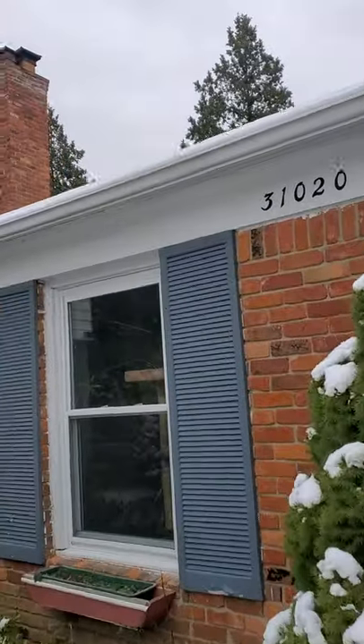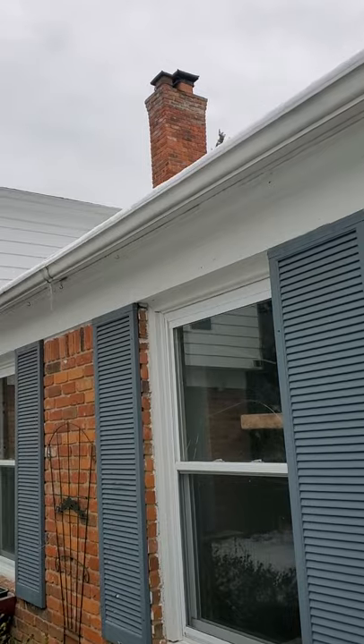What's happening there is you're losing heat. This is the importance of ventilation and insulation. When I did this inspection the other day, both of those things got called out — there wasn't any soffit ventilation. Right up what you guys would call the eaves or the overhang — that area is actually called your soffit. This house doesn't have any soffit vents. That's really where the cool air comes in; that's where your attic inhales, so to speak. And this house has a ridge vent up the peak of the roof — that's where the hot air comes out. A ridge vent is really an exhaust vent.